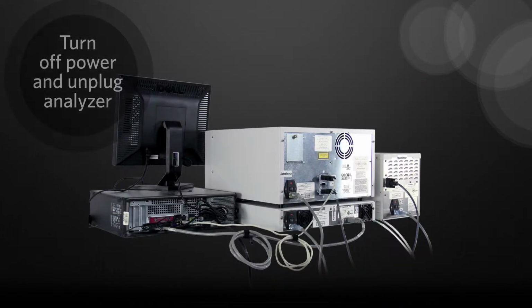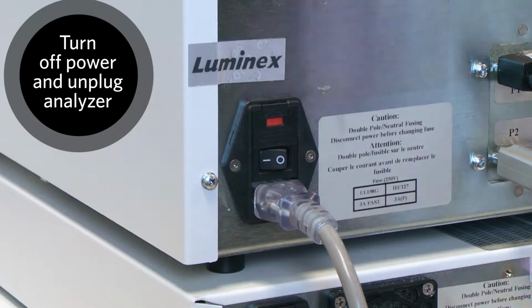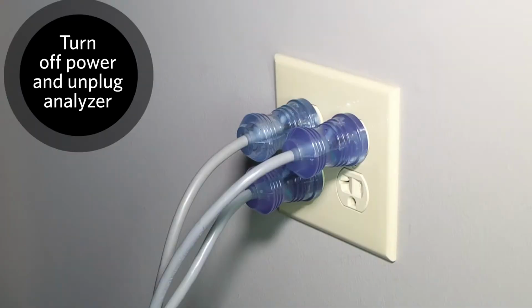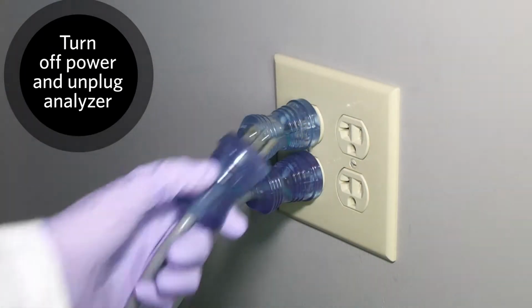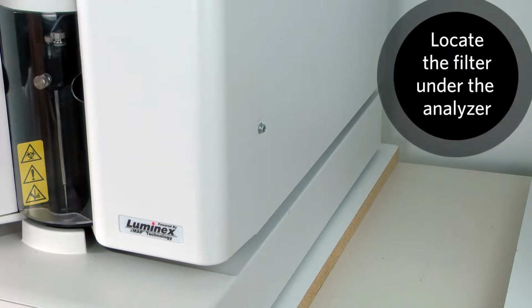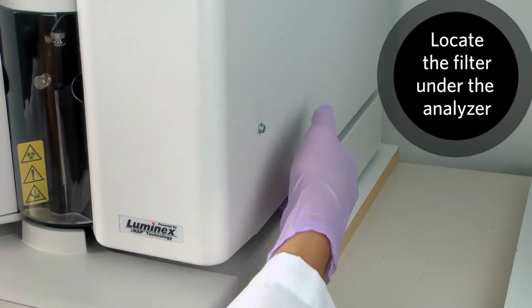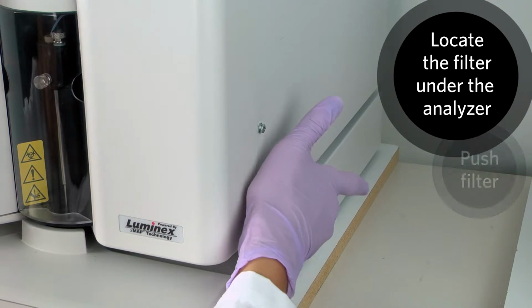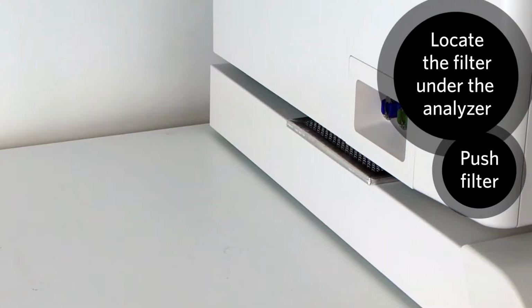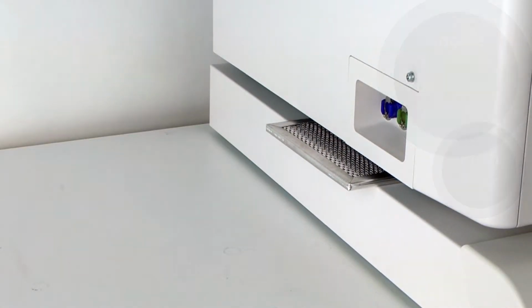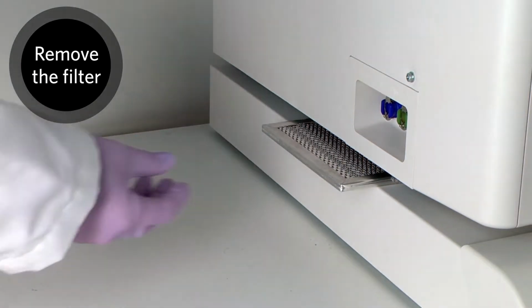Here's how to clean the analyzer vent filter. Turn off the power switch on the rear of the analyzer. Unplug the analyzer power cord from the wall. Feel under the right side of the analyzer to locate the filter. Push the filter toward the left of the analyzer. Remove it from the left side.